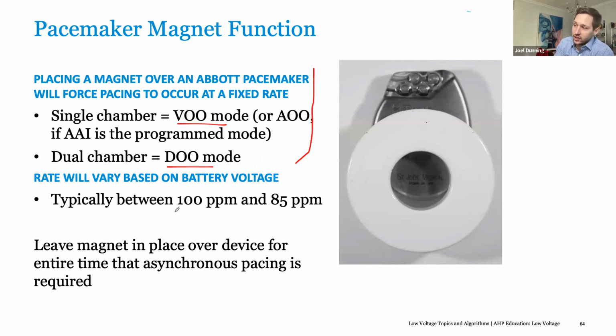So in Abbott devices, if you place a magnet over a pacemaker and it's 100 beats a minute, that means that it is generally a pretty good battery and they have some more life left on it. As you get closer to 85 beats a minute asynchronous, that indicates that the battery is nearing what's called ERI, where it needs to be replaced. So you can use that to evaluate, as well as using magnets during surgery so that you don't have to permanently program the device. As long as the magnet is over it, it will be in its magnet mode. Once you take the magnet off, it reverts back to a non-magnet mode.